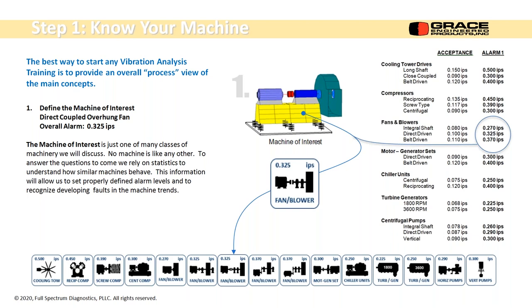The nice thing about having these real-time sensors that are bolted in place or magnet-mounted in place is that they'll continuously take data. And any subtle change from the mean level is going to be recorded. And as a result, I mentioned on Tuesday, the alarm levels are the mean level plus three sigma. So statistically, that's three standard deviations above and below the mean curve for the data that it calculates. So as it goes in, the database calculates a new mean level based on old data and the current data, and new statistical data, and your alarm curves get better and better.